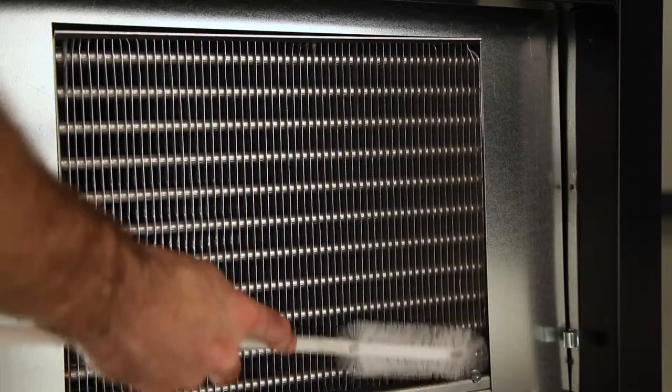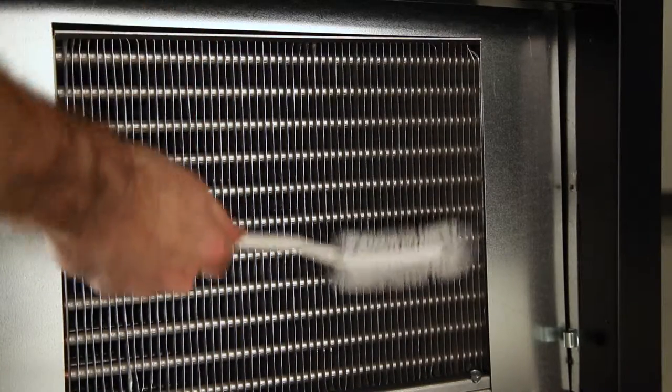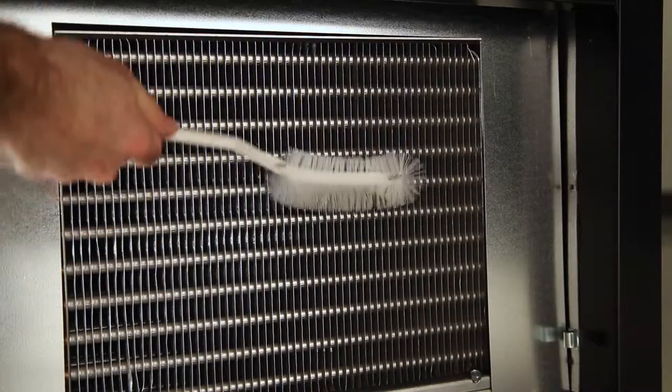Then clean off the condenser coil with a stiff bristle brush. Move the brush up and down the coil and never side to side as this could bend the fins on the coil.